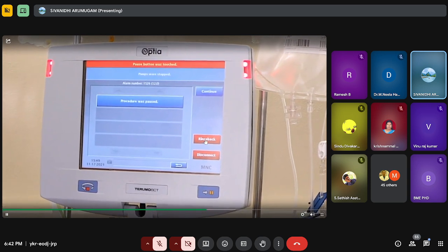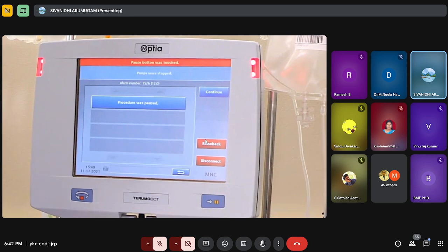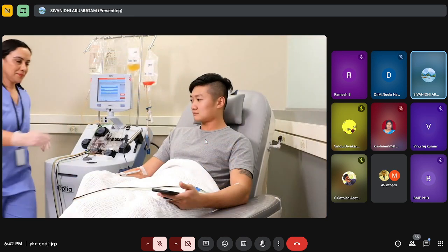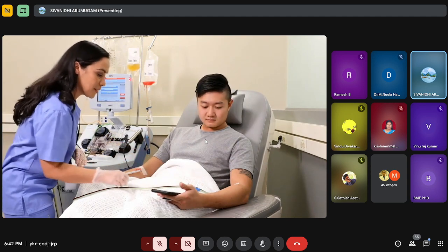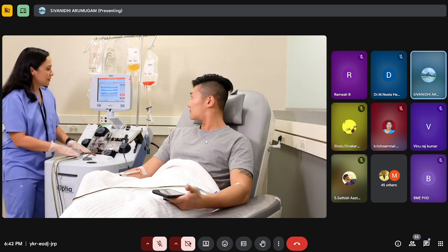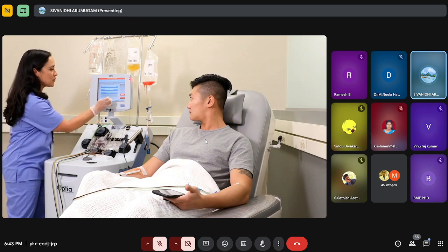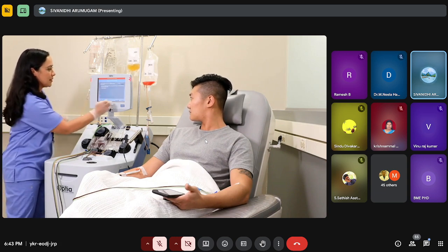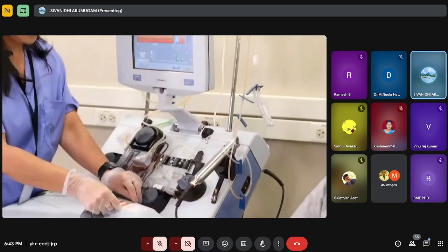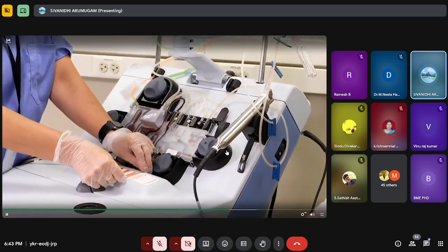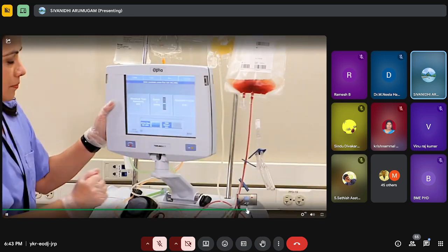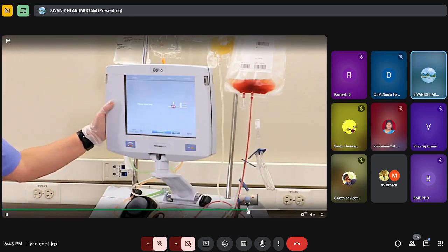The system allows operators to easily troubleshoot and optimize procedures. If the system detects an operation error or a potentially unsafe operating condition, it triggers an alarm. The alarm screen shows all the possible causes of the alarm. The system may stop the pumps or the centrifuge. The operators can customize each procedure performed by entering a run target. At the end, the blood remaining in the set is returned back to the patient.